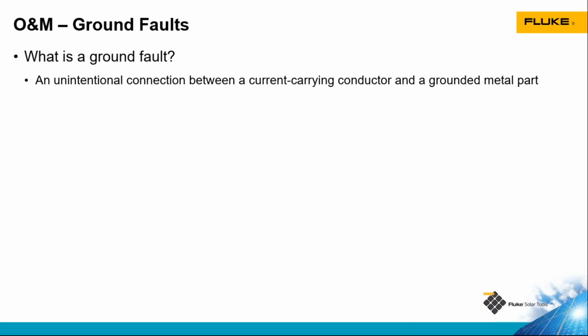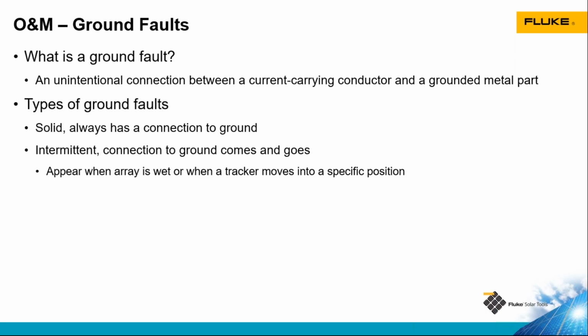One of the most common issues in solar arrays is a ground fault. A ground fault is an unintentional connection between a current carrying conductor and a grounded metal part. There's many causes of ground faults. There are two main types of ground faults. Solid ground faults are low resistance connections that are always present, so that fault is always there. The second type are intermittent ground faults. They have a higher resistance connection.